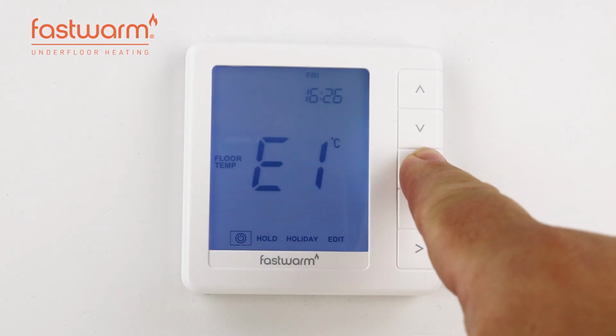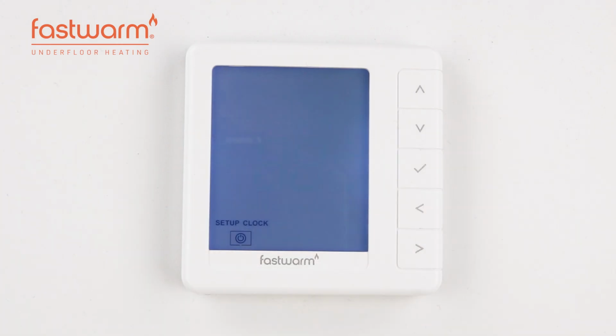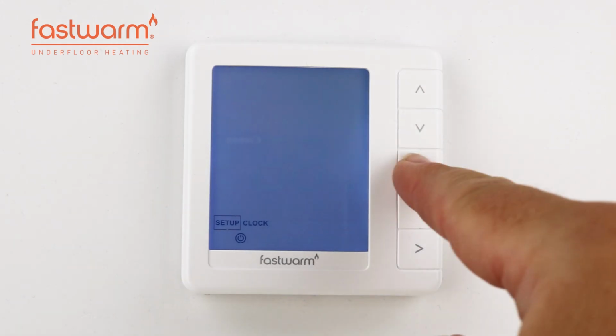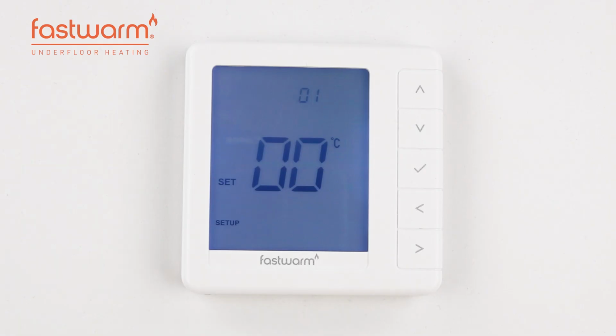E1 error. The E1 error code indicates that the remote floor probe is not connected. Check the wiring and ensure it has been installed correctly. To clear the E1 error, press and hold the tick button on the highlighted power icon. Press the up arrow to select Setup, then press tick to enter.